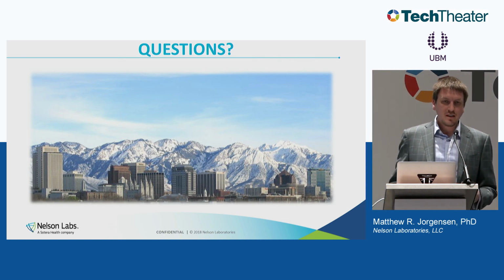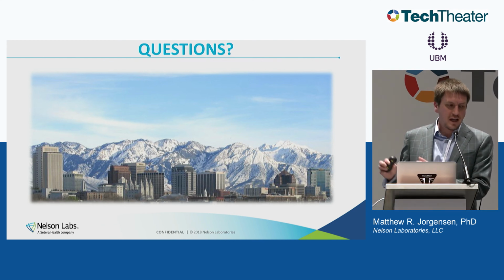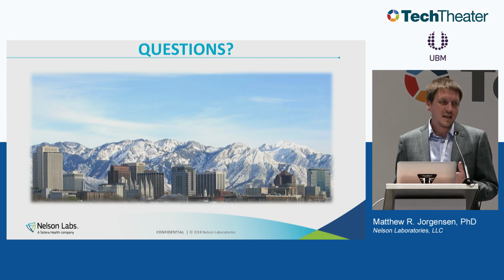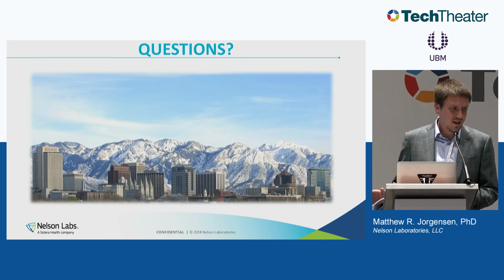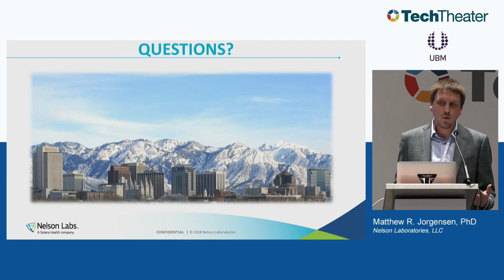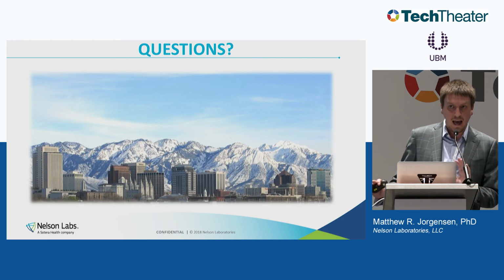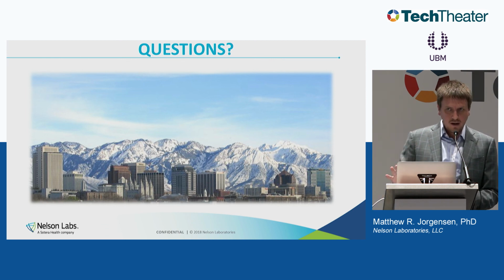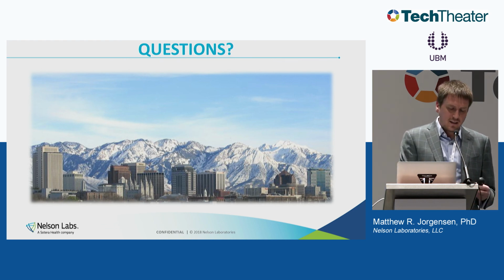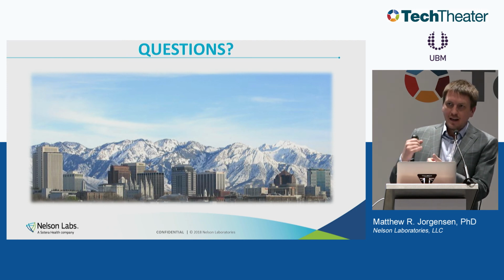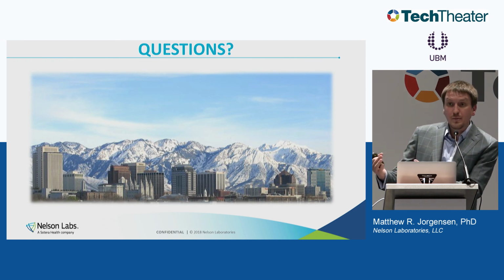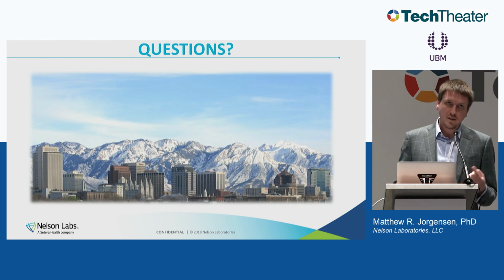Yeah. So the comment was, she's heard in the past from other webinars and things like that that chemistry and evaluations were becoming more and more important. And do I have any examples where somebody has done just a straight paper evaluation, no testing, and been successful? And so the short answer is yes. This comes across my desk maybe once a month, maybe once every 2 months, where we do a project where there's no testing. No new testing at all, right? And in these cases, it's a material that's very well characterized, a metal material, and they have data like the previous cleaning validation data that demonstrates that residuals aren't an issue. So if you're in that category, let's say a nitinol stent and a well-documented cleaning validation, then that's enough. Or it has been enough in the past, right? So we've done that. Or the example I gave before, specifically a titanium knee and a good cleaning validation, then we've been good. So it is possible with only written evaluation.